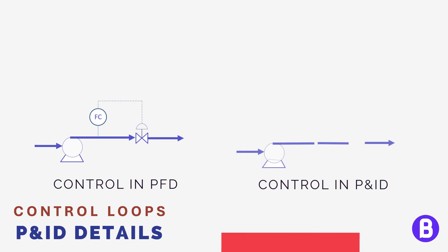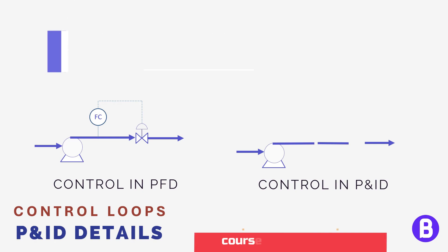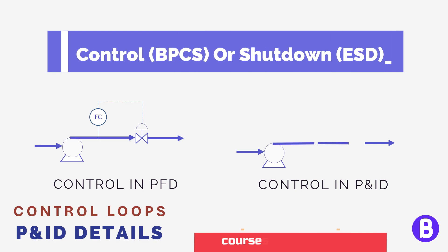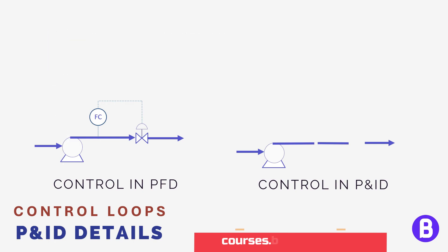So if this is a control loop of a pump discharge in the PFD, in the P&ID we would need to show more details. As we said, instruments send their readings to the downstream system. This system can be either the basic process control system, which is BPCS, or it can be the safety instrumented system, which is SIS, or in other words ESD for emergency shutdown.